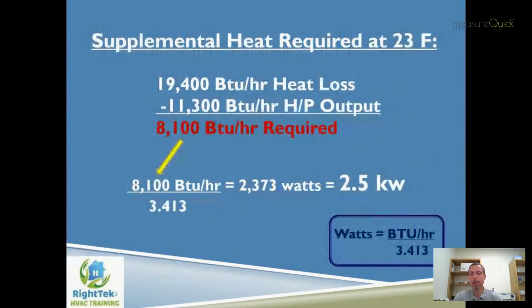So if I've got 8,100 BTUs per hour, I need to make up. There's a little watts to BTUH conversion formula I've got on the bottom right of the slide that you can hopefully see there. So I take the BTUs per hour and divide it by 3.413 to convert it over to watts. And I'll see that I need roughly about 2,400 watts, and about the smallest nominal heat strip you're going to find that accomplishes that is about a 2.5 kW nominal heat strip. So if I were only sizing to provide supplemental heat and nothing more, then that would be approximately the minimum size electric heat strip that I should put in.